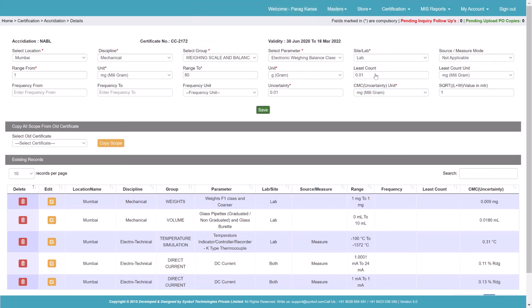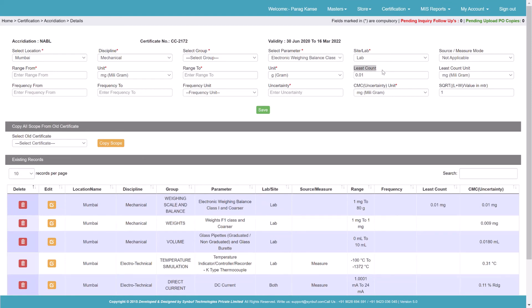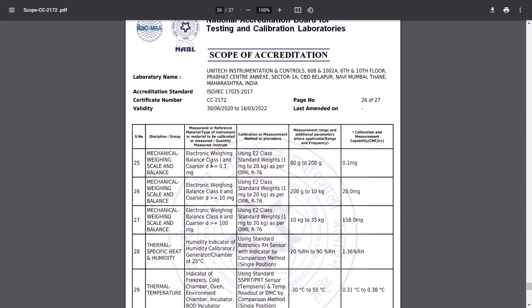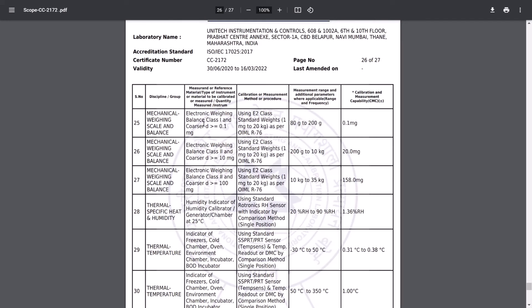Because of this least count, the software will validate it. Those weighing balances that are more accurate or having a more precise least count than 0.01 — the accreditation scope will not be applicable for those units under calibration. So we cannot issue the certificate for those having a more precise least count compared to 0.01 or whatever least count we have entered.